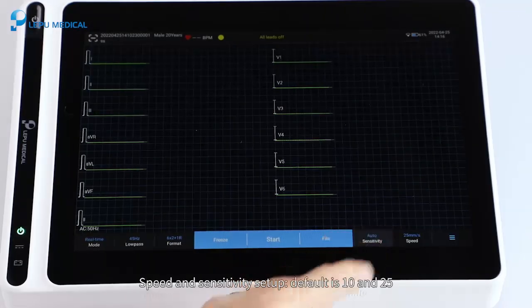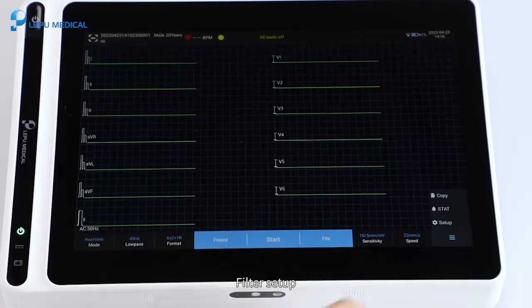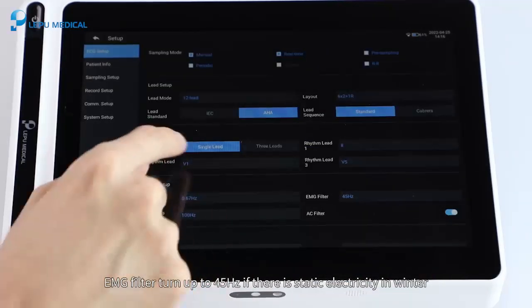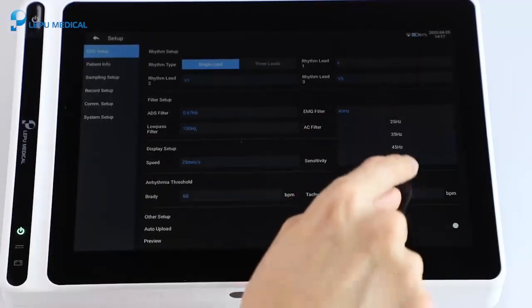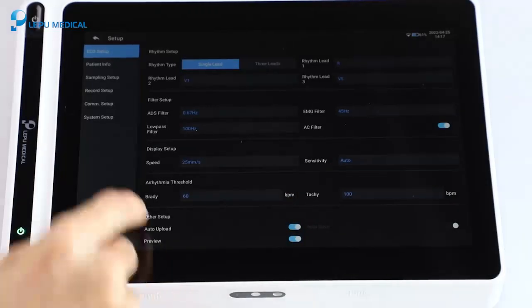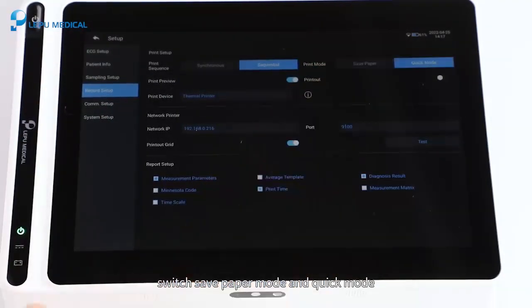For speed and sensitivity setup, the default is 10 and 25. For filter setup, turn the EMG filter up to 45 Hz if there is static electricity in winter. For print setup, switch to save paper mode and quick mode.